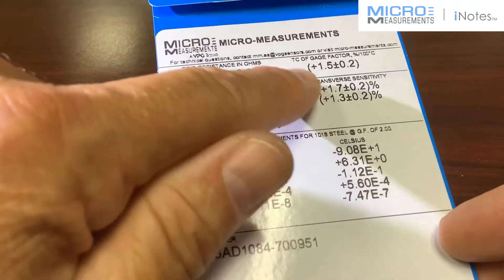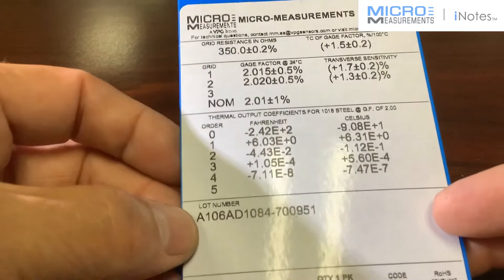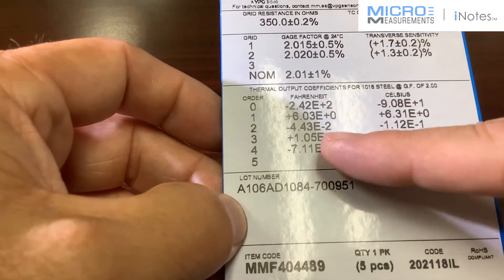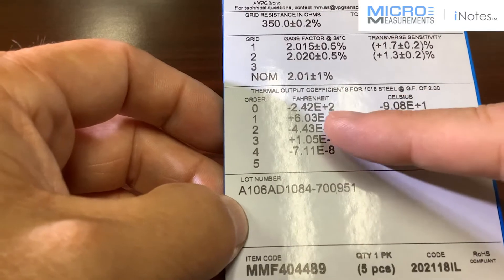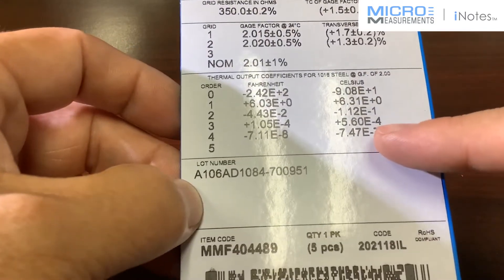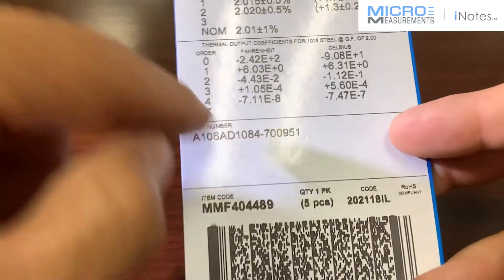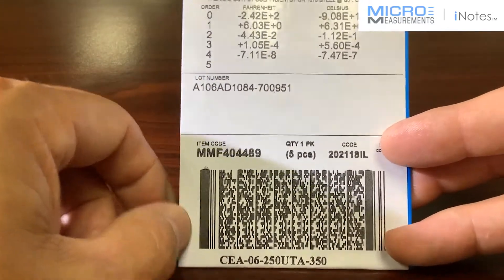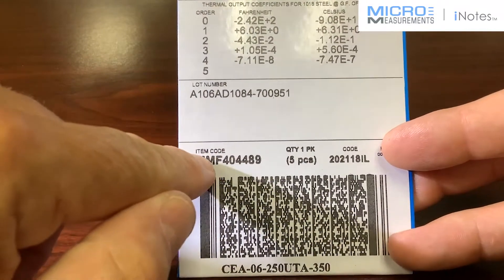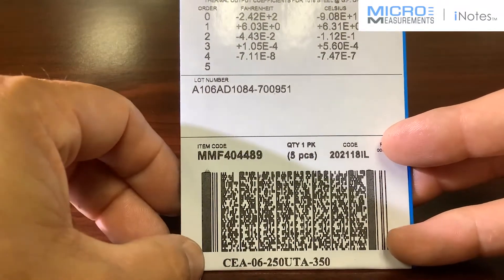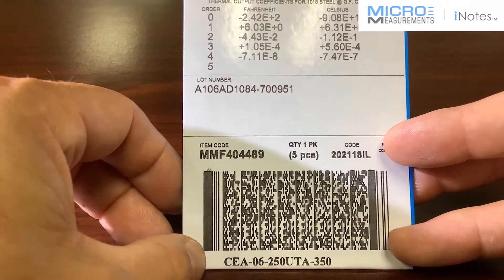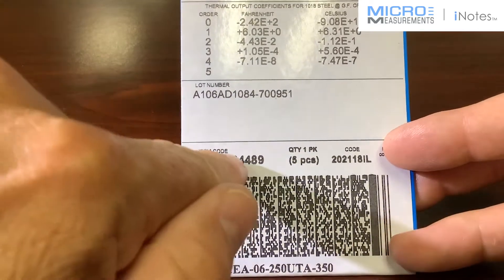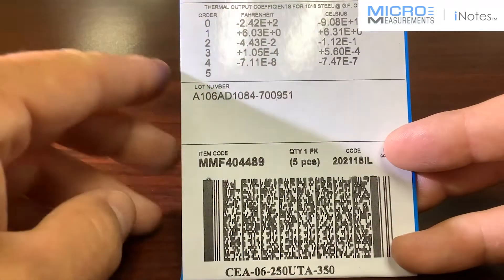Transverse sensitivity, just over 1% for the two grids, and as we work our way down, you'll see the thermal output coefficients. It's a fifth-order equation. You'll see in degrees Fahrenheit and degrees Celsius. A lot number, which is important for traceability, and then you'll get down here to the bottom, and you'll see an item code. Now, this will be a new item code for these T-rosettes, so if you're familiar with the 250 UTs, this is now a UTA, and it will have a new item code to reflect that new construction.